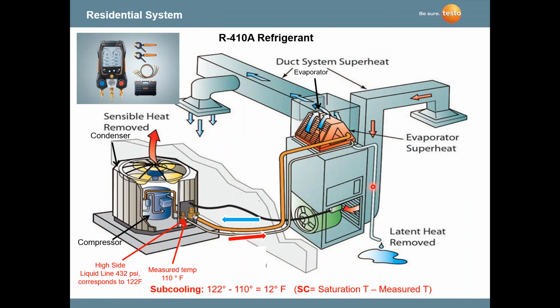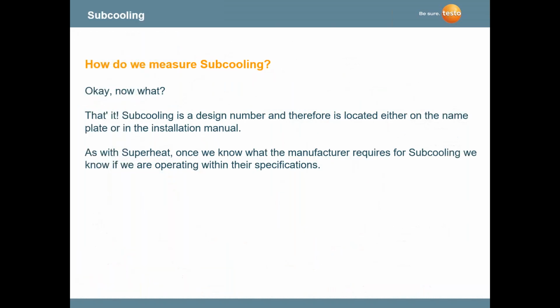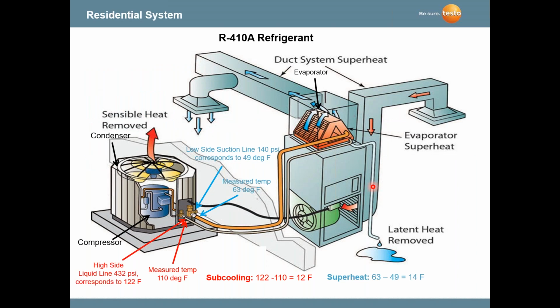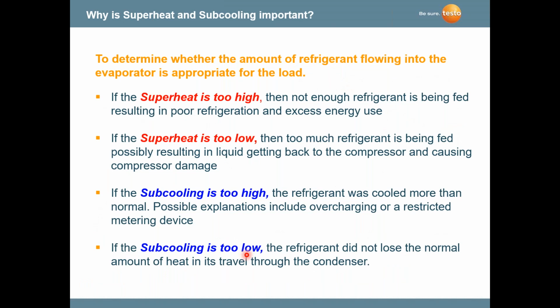Again, we're looking at where we're taking the test on the high side of an air conditioning system. And subcooling is a design number. Therefore, it's found in the installation manual or on the nameplate. So it is a requirement. It is supplied by the OEM, the equipment manufacturer. So we have a lot of measurements we can do, and you can see that using a digital gauge is a lot quicker, faster, and more accurate because we're looking at everything simultaneously. We're looking at the superheat and the subcooling together if we want to. We're looking at low side and high side pressures, low side and high side temperature measurements, and we're doing all the calculations.